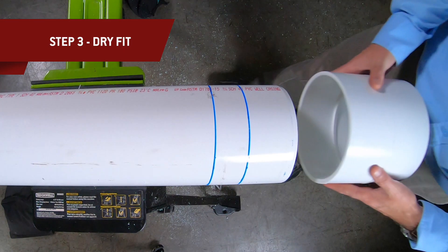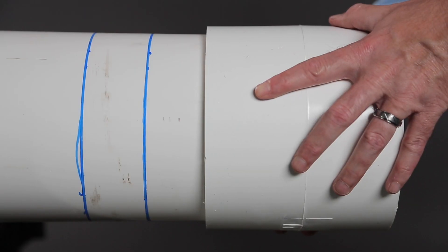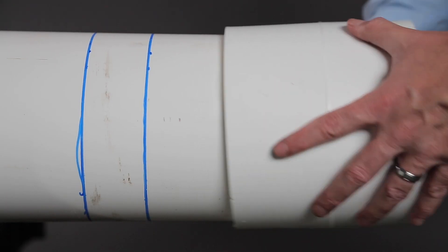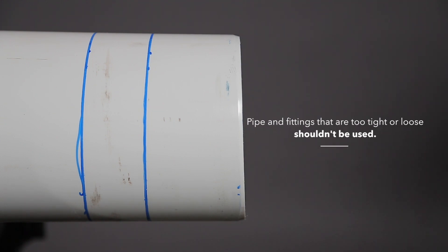Do a dry fit. With light pressure, the pipe should go one half to two thirds of the way into the fitting hub. Pipe and fittings that are too tight or too loose shouldn't be used.